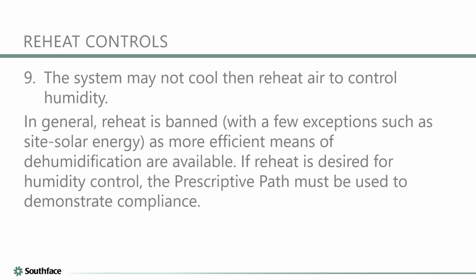So reheat in general is kind of banned out of the code unless you have very tight parameters for your humidity and temperature controls, like you absolutely need to hit that particular spec. It is not a good choice for something like a general office building. Yeah, and that's a good point too. When we're talking about exceptions here with reheat, it is so banned that we aren't making exceptions for the archives or the libraries. In fact, the code just says if you need reheat, sorry, you can't use the simplified approach. You have to go down the prescriptive path. So no exception is really made on reheat except for site solar energy and a couple others. But typically it is basically outright banned. That's an interesting thing given how many exceptions there are in the code.